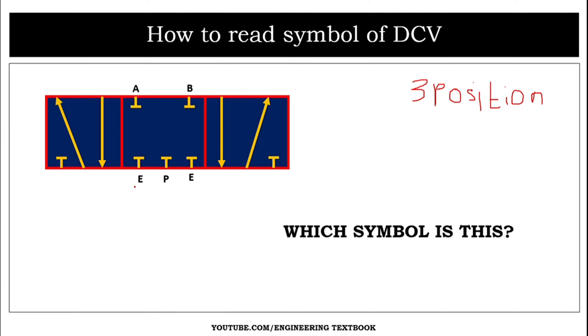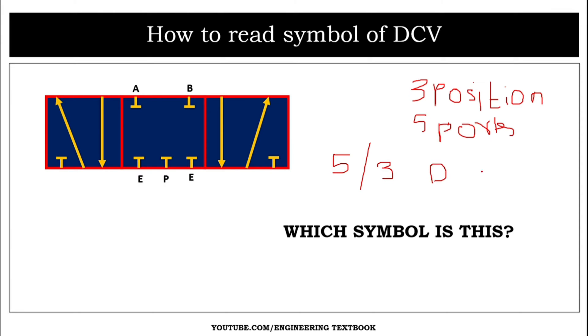We have to count the number of ports in only one particular box. Let's count: port A, port B, port E, port P, port E again — so one, two, three, four, and five. There are five ports. As there are three positions and five ports, this is a five by three direction control valve.